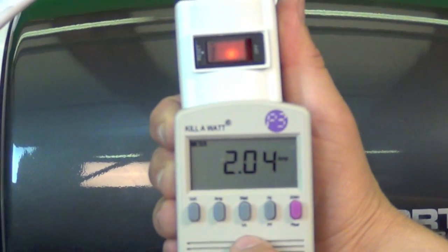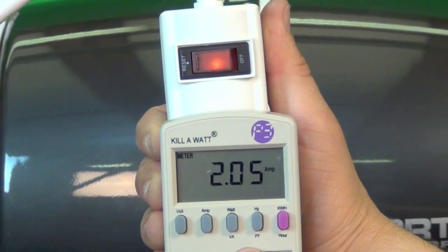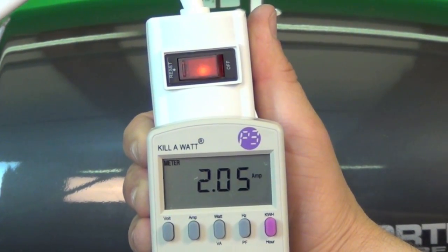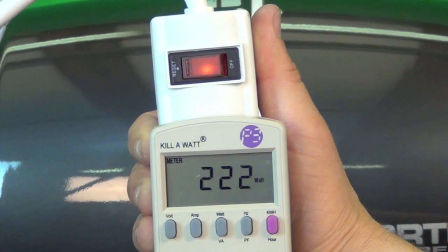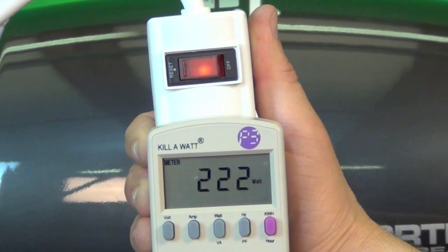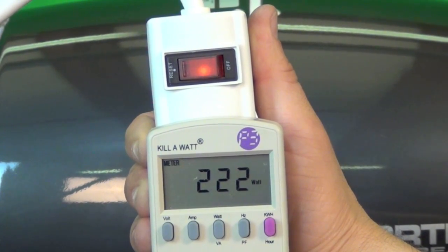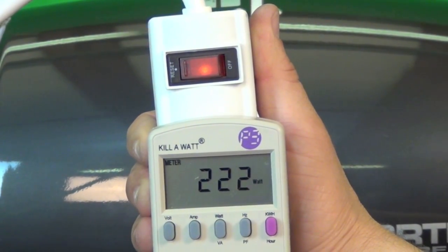So here's our standard inline fan. As we can see, it's running about 2 amps. This is an 8 inch fan with a 740 CFM capability. It's drawn about 220 watts on the 120 volt. So this standard inline fan is running about 220 watts at about 740 CFM.